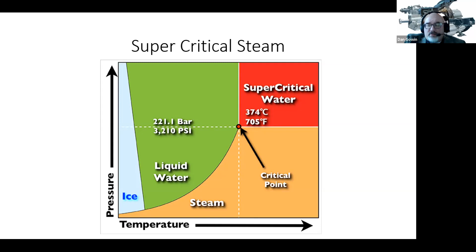The supercritical point for pentane is about 196.5 degrees Celsius, which is 386 degrees Fahrenheit. That means you only need to drill your geothermal wells deep enough to get water at 386 degrees Fahrenheit to make your pentane go critical. At 227 degrees Celsius, or 440 degrees Fahrenheit, that supercritical pentane at 100 bar, which equates to 1,450 PSI, can run really great turbines like the one behind me.